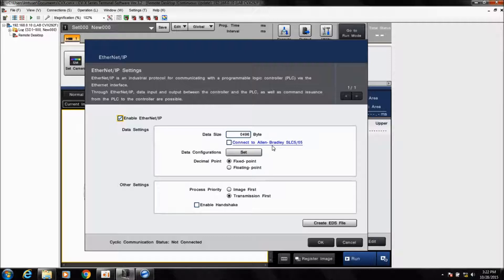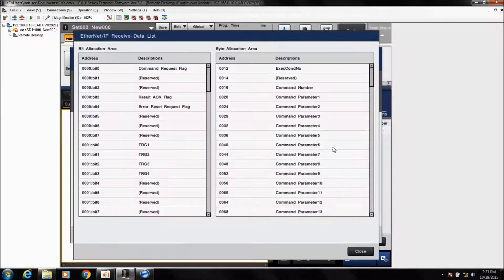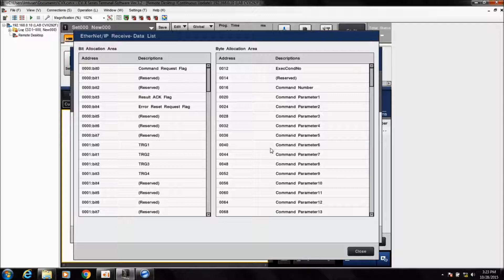If you're connecting to an SLC or MicroLogix type PLC, you can check this box, but really the only thing that changes is the data size — it lowers it down. Under data configurations, you can click Set, and if you want to view the data allocation list, just click View List, which will show you all the different IO mapping done over Ethernet IP.